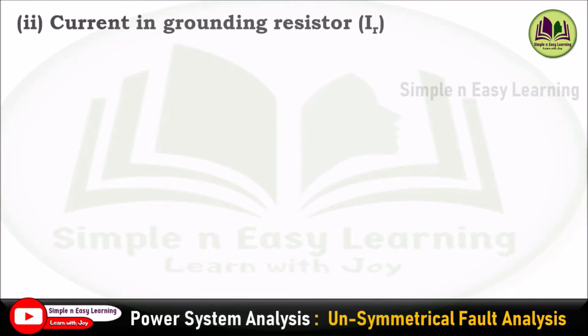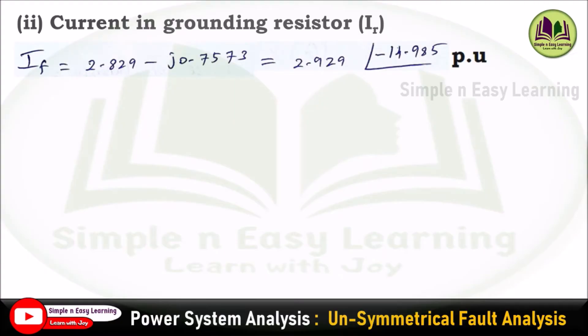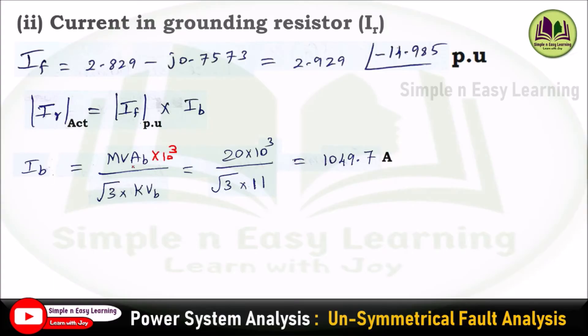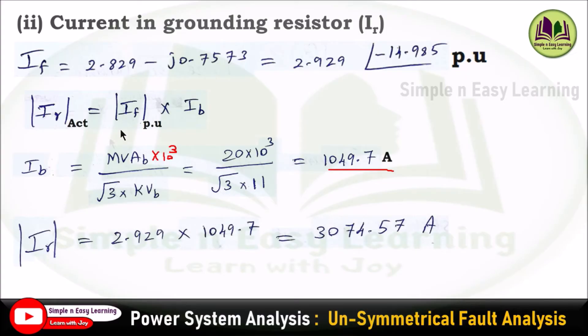Next, determine the current flowing through the grounding resistor IR. The fault current flows through the grounding resistor, so IR equals the fault current. The actual value of fault current = per unit value × base current. Base current = (MVAB × 10³) / (√3 × KVB) = (20 × 10³) / (√3 × 11) = 1049.7 ampere. Therefore, the actual current through the grounding resistor = 2.929 × 1049.7 = 3074.57 amps.